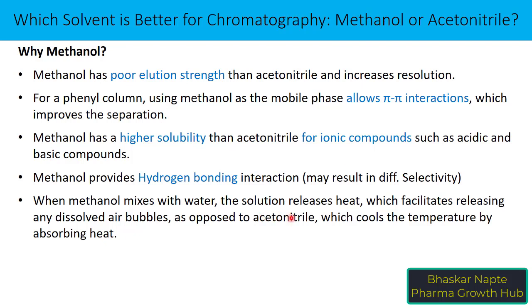When methanol mixes with water, the solution releases heat — it is an exothermic reaction, causing a slight temperature increase which facilitates the release of dissolved air, promoting deaeration. In contrast, mixing acetonitrile with water is an endothermic reaction, causing the temperature to drop, which may lead to absorption of air. If deaeration is not done effectively, the acetonitrile-containing mobile phase may create air bubbles frequently, resulting in retention time fluctuation and baseline disturbance.